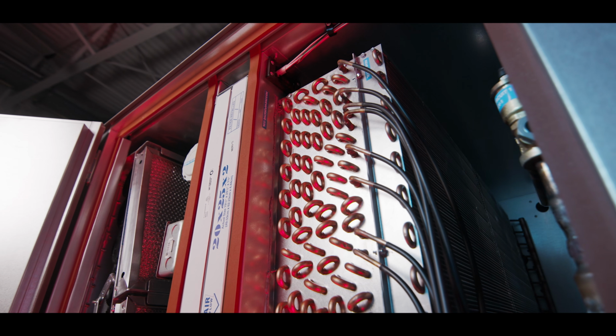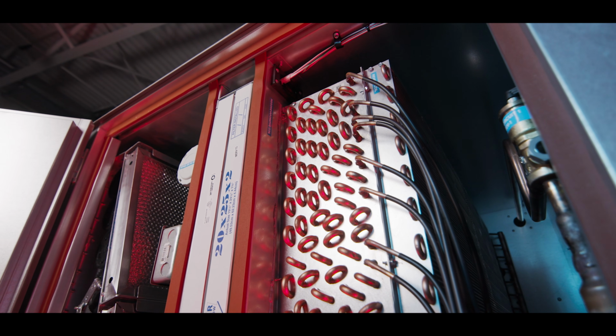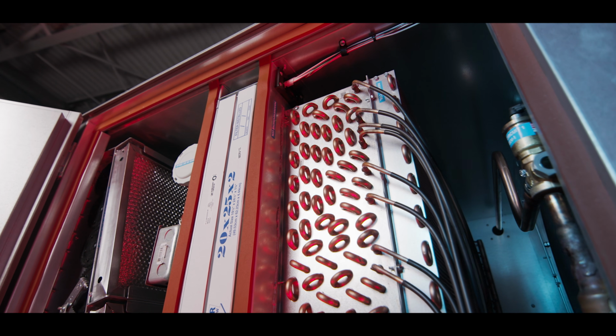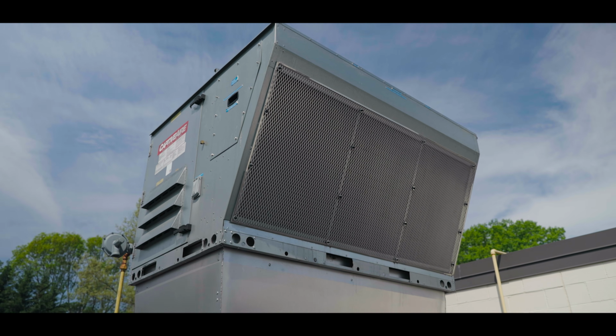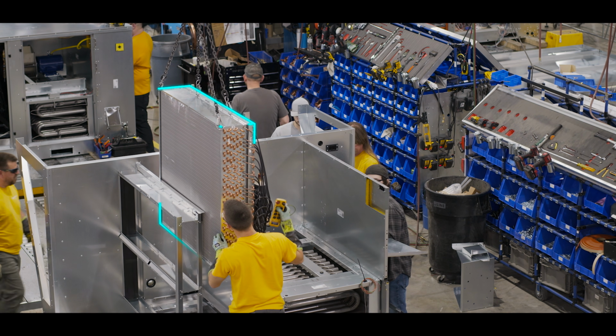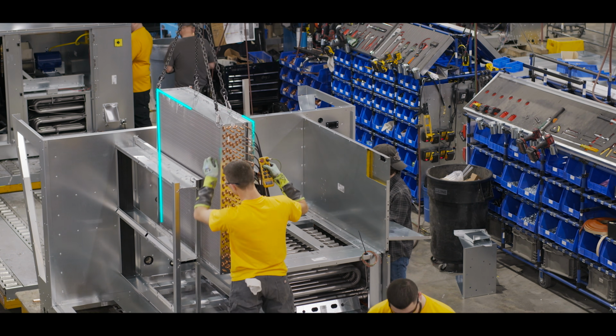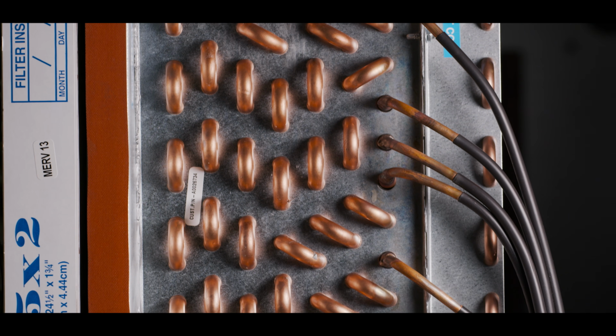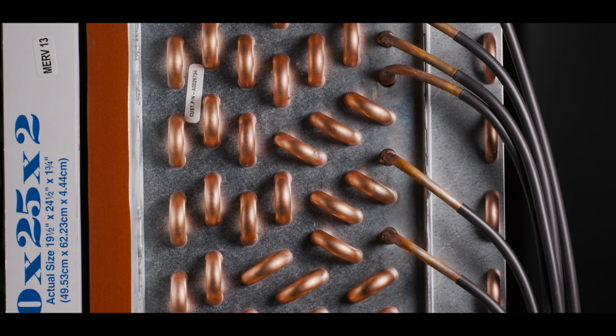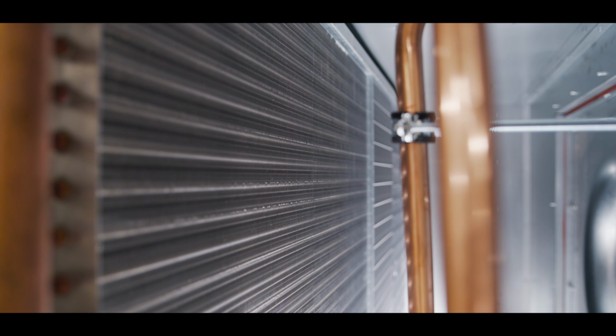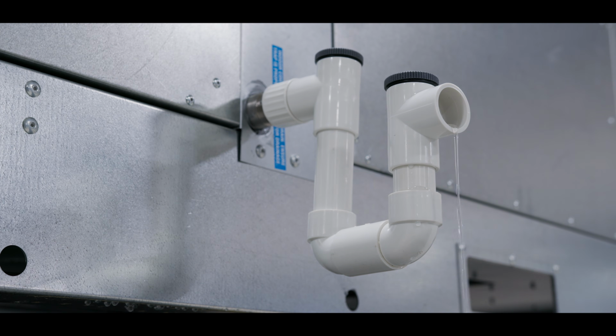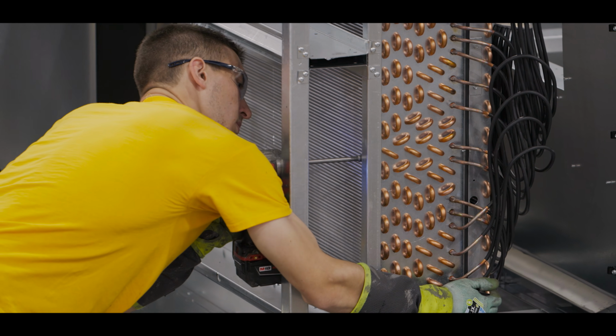This is actually very important, partly due to what sits just upstream of these wheels. If you look at a standard RTU versus Paragon, one major difference will be that indoor coil. If you look at Paragon, the coil is very thick. And you may ask, well, why do you need such a heavy-duty coil in this unit? And the answer is, as that air passes through that coil, there has to be enough residence time for the air to cool down and water to drop out of the air, moisture to drop out of the air. So it's thicker than a standard RTU because we process that outdoor air and remove that moisture correctly.